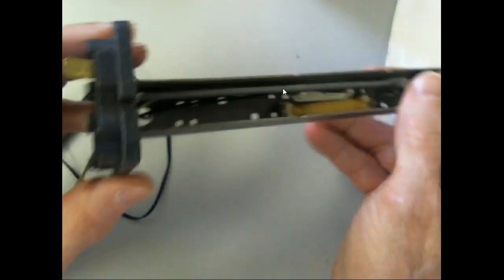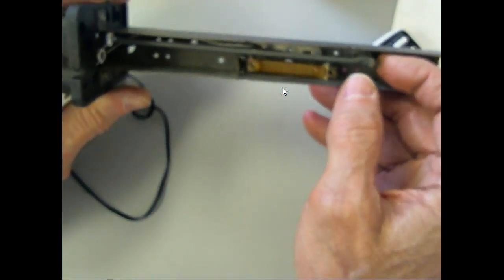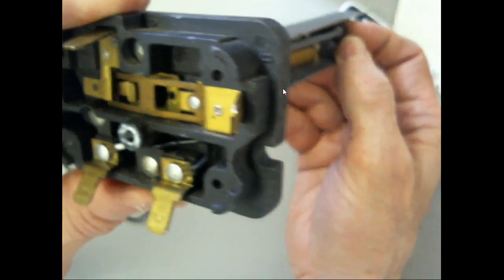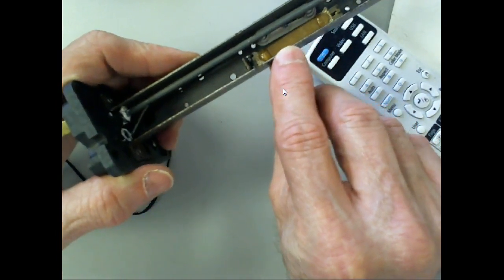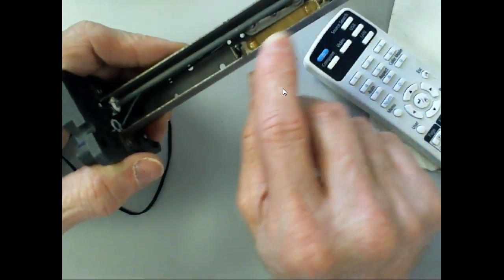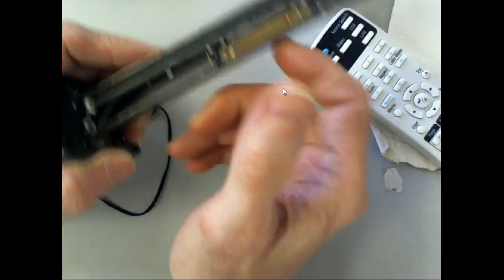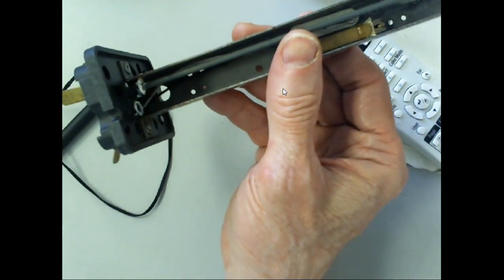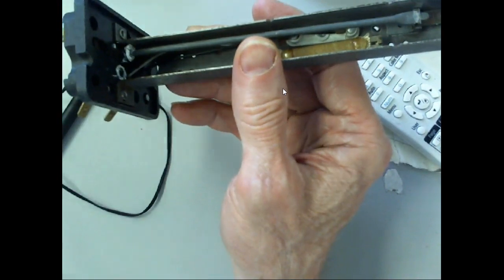So what happens, there was a switch back here in the back. When this got up to a certain temperature, it would warp and cause a contact to break back here in the back. This right here is an RTD. So it's nothing but a what? A bunch of wire just looped. And then what they do is they put it in series with a resistor or inside a Wheatstone bridge, and they just measure its output.